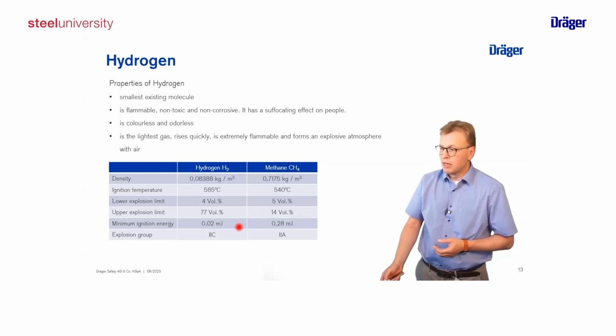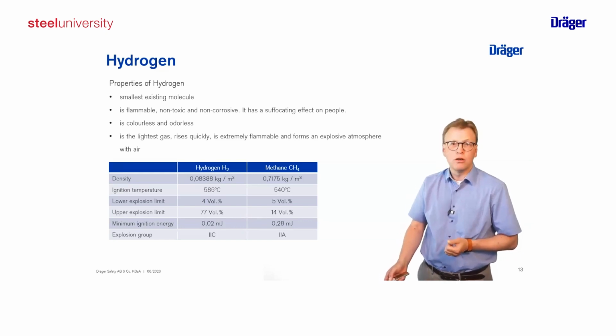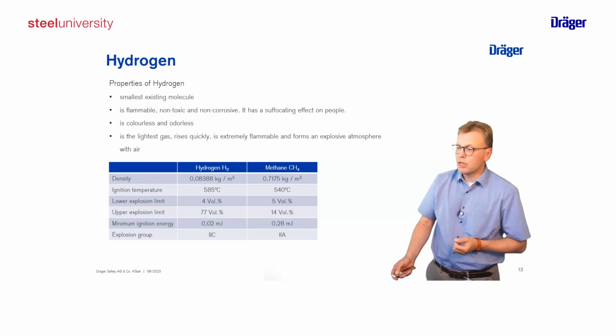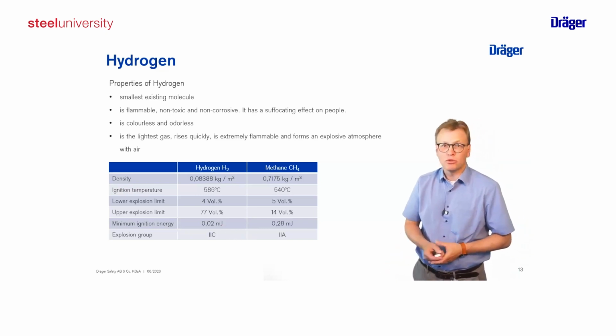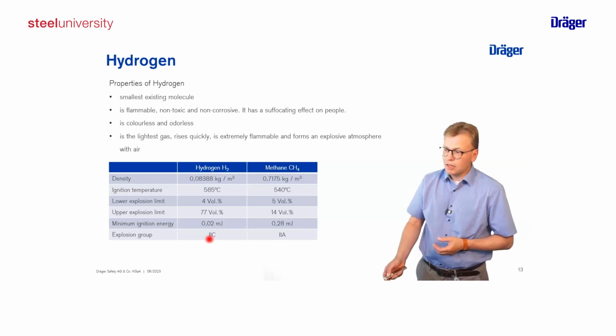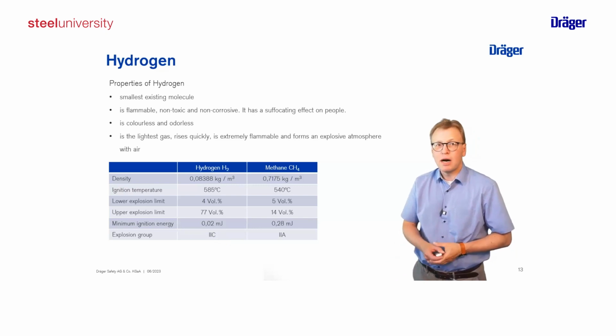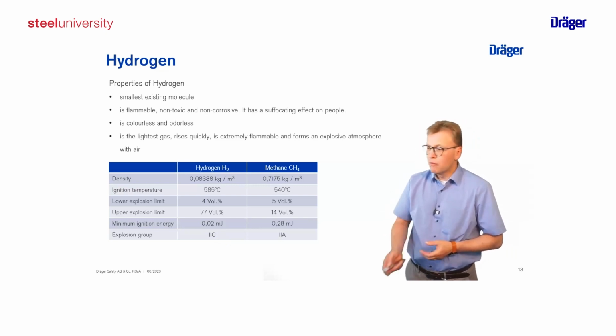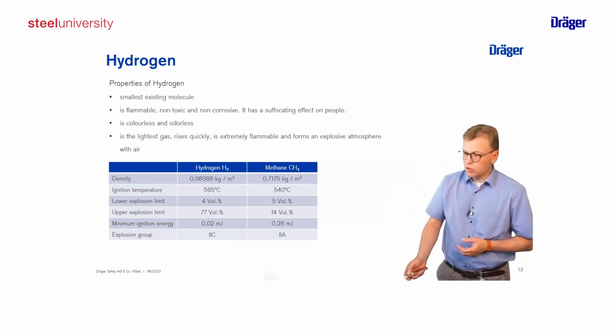And there we see, in terms of what we are used to, methane. So only 0.02 millijoule are needed to ignite hydrogen. So very, very little energy. That leads to the effect that equipment which should be used in this area needs a marking or a certification for IIC, compared to methane, so 2 classes higher.